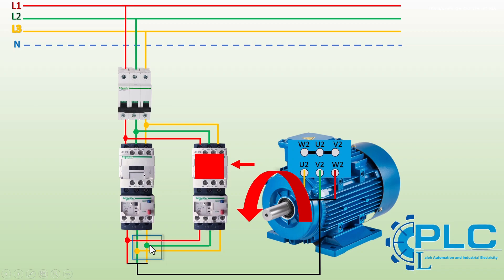We must ensure that both contactors never activate at the same time, as this could create a short circuit, which is very dangerous. To prevent both contactors from activating simultaneously, we need an interlock system in the control circuit. The interlock ensures that when one contactor is active, the other is automatically blocked — even if I press the reverse start button, it won't activate the reverse contactor while the forward contactor is already running. Now that we have completed the power circuit wiring, let's move on to the control circuit.